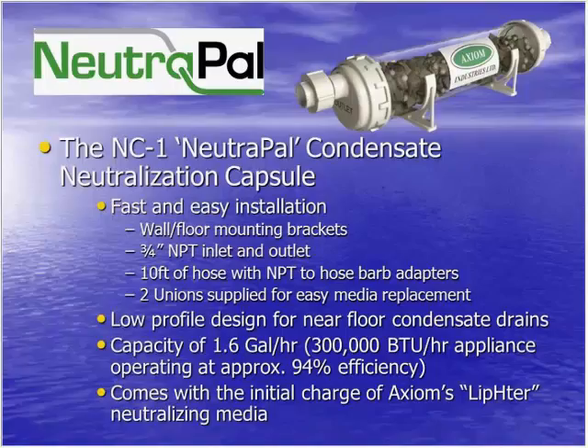Some manufacturers may not like to admit it, but there are particles of the heat exchanger and such that also find their way into the trap and get collected in here, which can prevent contact with the media. So that's one reason why we also make our capsules clear. It gives early indication that if something like that is happening, it can be serviced at a regular basis. You can actually flush it out and clean it out, or just replace the media.